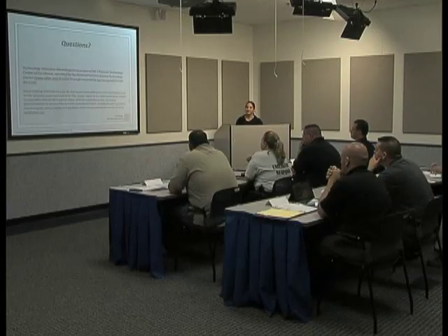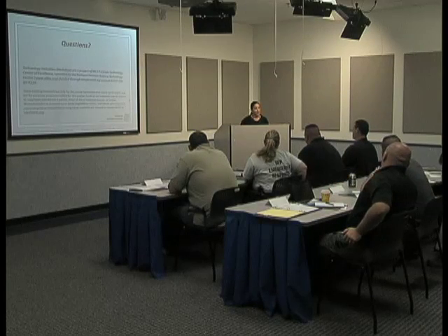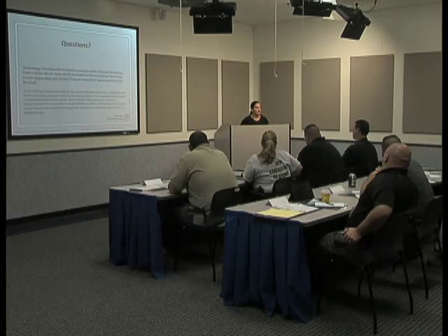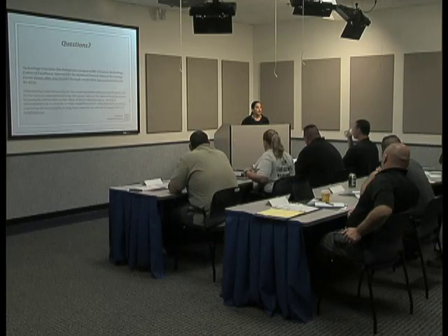Do you have any questions? So the Aegis uses a nickel-63 for ionization? Yeah, so it's not a glow discharge. It's radioactive, the nickel-63.